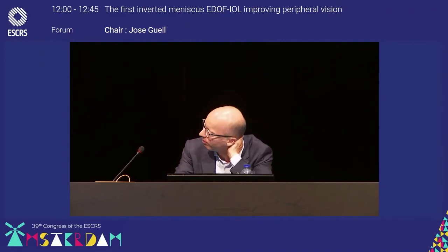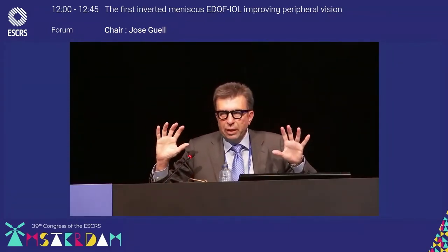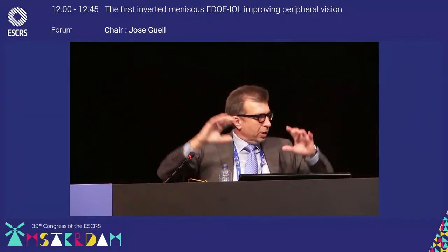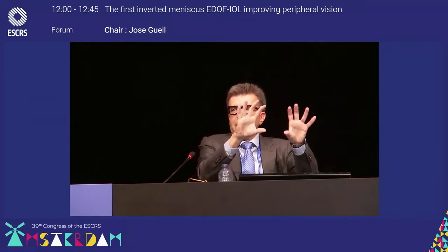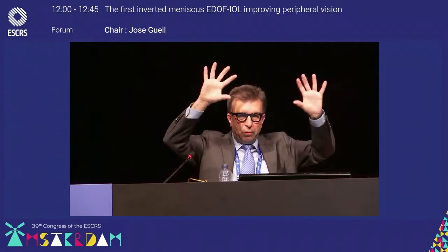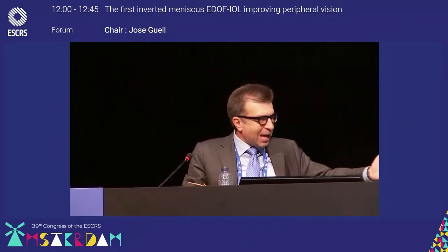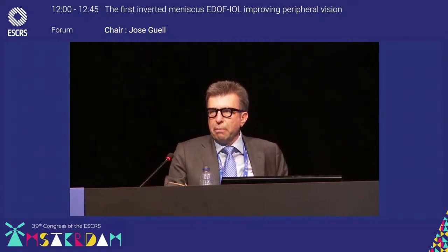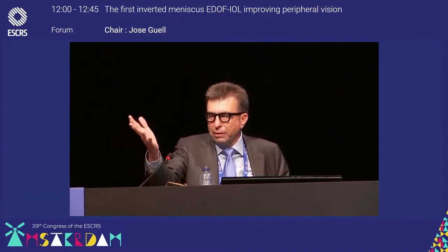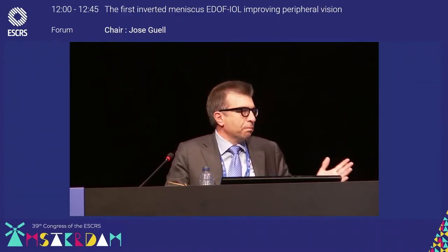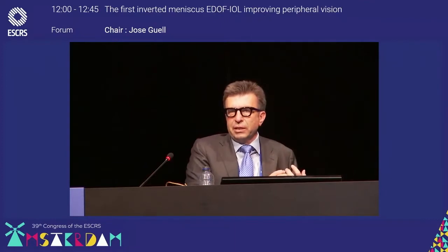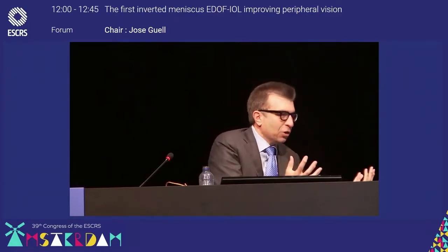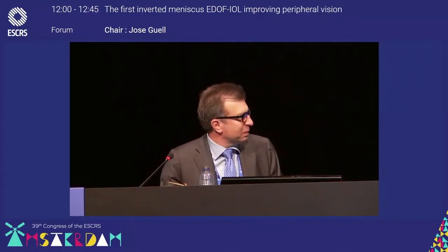All these photopsia phenomena usually appear at much larger eccentricity. We tried to improve optical quality in what we call mid-periphery, and we were not initially concerned about the very far periphery. But I think it's like an extra bonus — the particular shape of the lens is also producing a good effect to reduce these photopsias. They are not very common, but as you said, for some patients it's really very bad. We don't have proof, but our feeling is that these lenses do a better job preventing peripheral dysphotopsias, even though we were not thinking about that in the design phase — it's like an extra benefit.